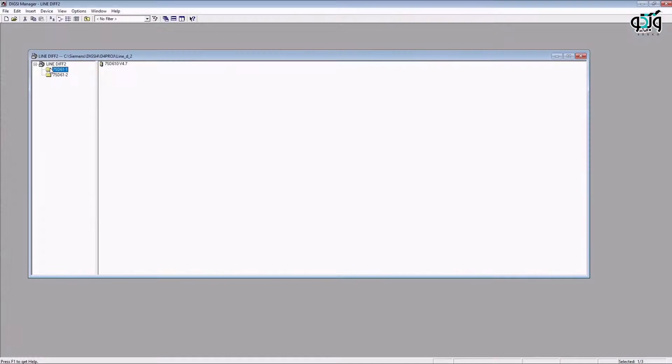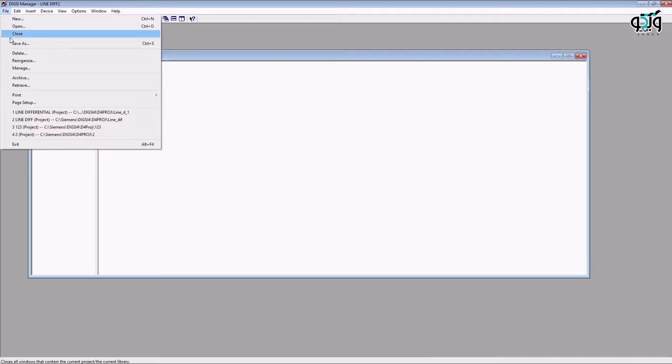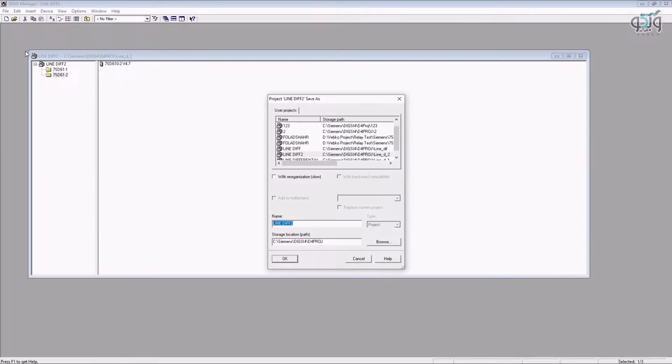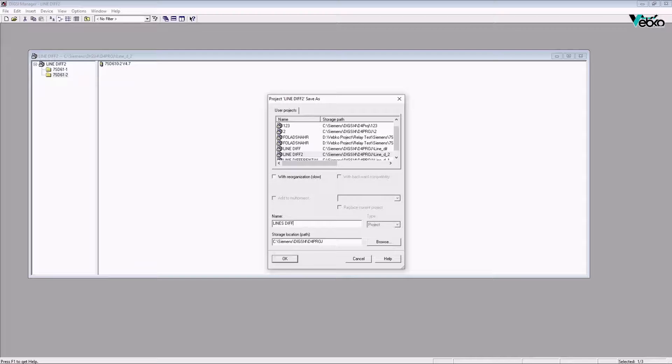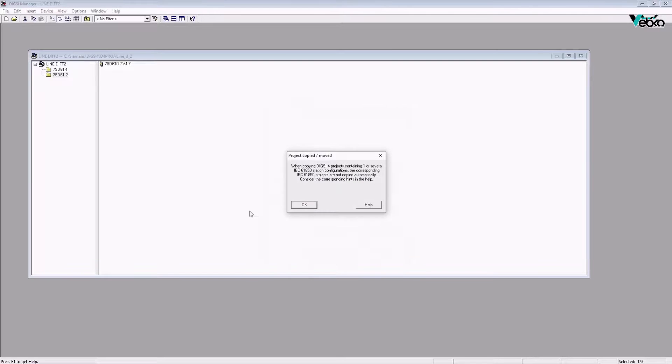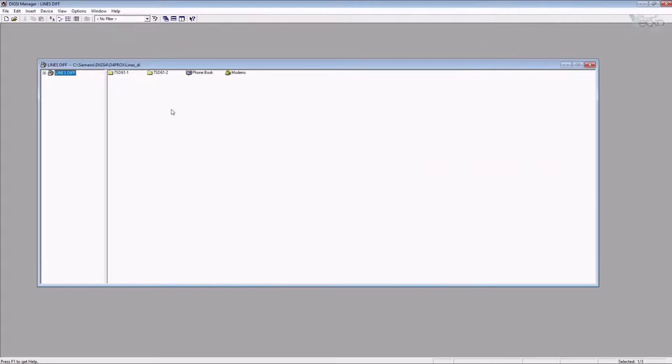Software preparation - in software section, before anything, it is necessary to connect to the relay and save settings and config files as well as the records submitted for event and disturbance somewhere safe so that if there is a problem, they can be used as a backup. In the next step, export the file needed to enter the test device from the relay.